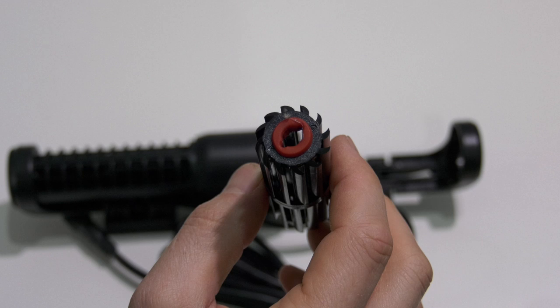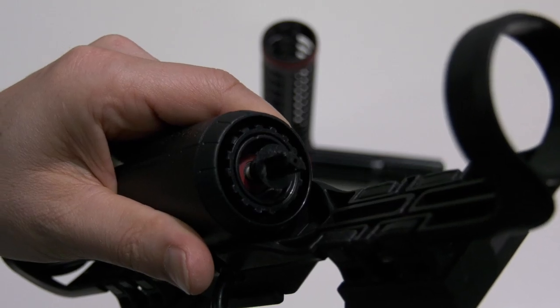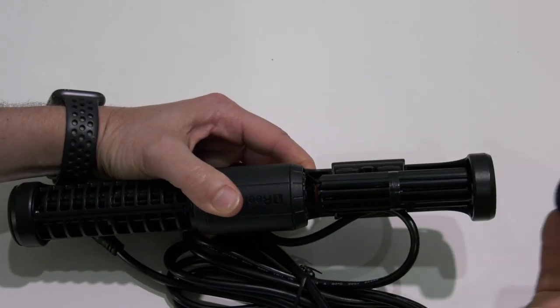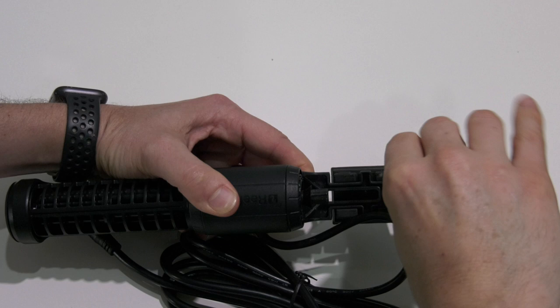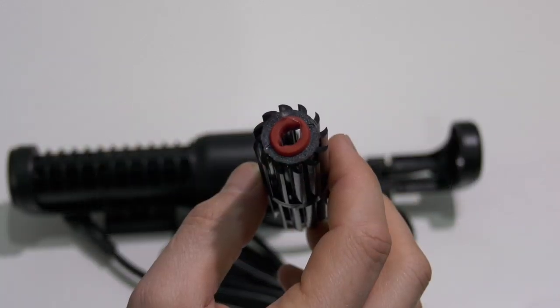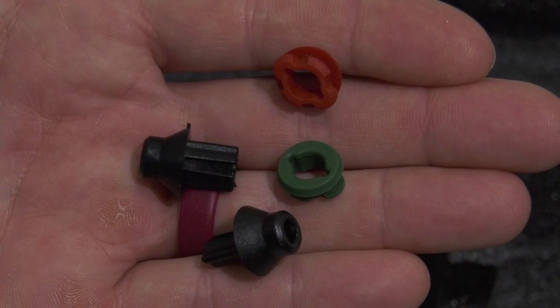One part about gyre pumps that always bothered me was how tedious the servicing of the pumps were. I'm glad to report that both models have new and much improved bearings. These bearings make the pumps very easy to service — just pull out the cover, remove the paddle, and the bearings are readily available for cleaning or replacing. The bearings are also color coded for right or left sides, making replacement that much easier.